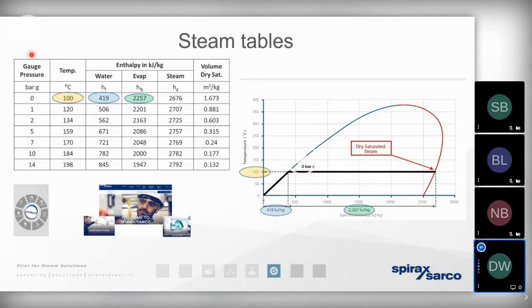Now that could be the pressure that the steam is being generated at in the boiler. It could be the pressure of the steam in the distribution pipework, or it could be the pressure of the steam at the heat exchanger. And we also remember that steam has got a pressure to temperature relationship. In other words, if we know the pressure that the steam exists at, we know its temperature. So if we're distributing steam at 10 bar gauge, that steam will have a temperature of 184 degrees.